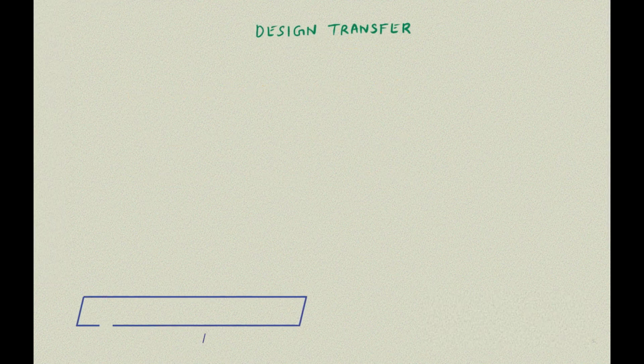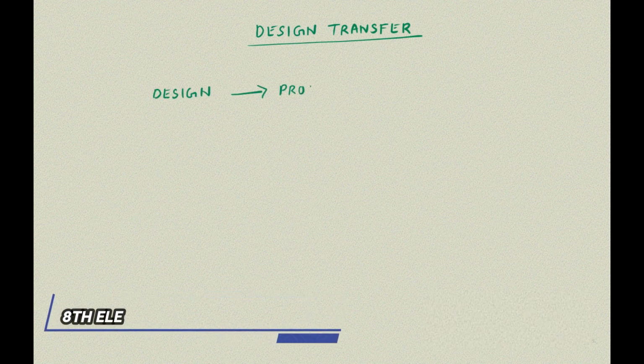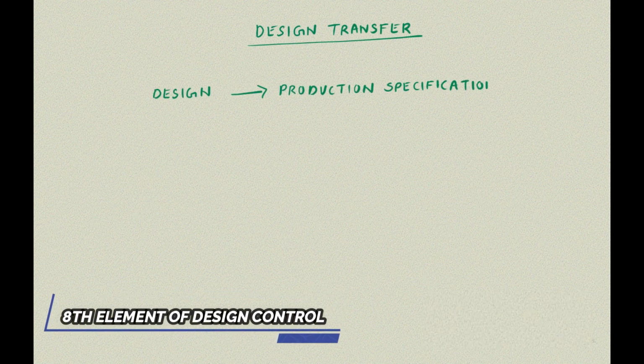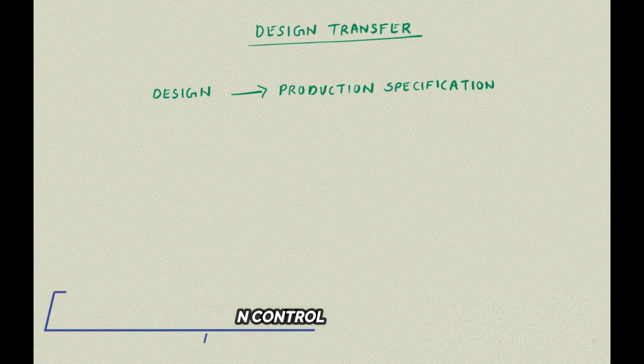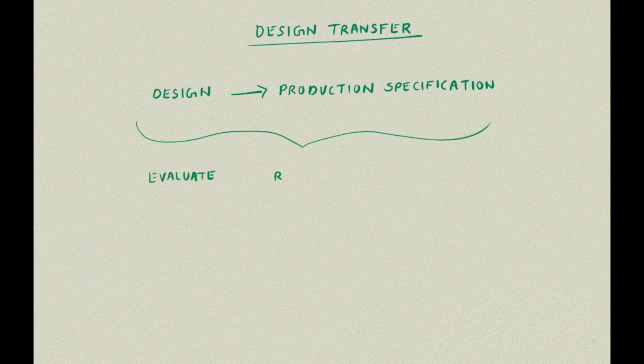Next is design transfer. The company should establish and maintain a procedure to ensure correct design transfer to the production specifications. Basically, we ensure that the design of the medical device is correctly translated to the production specification at this stage. So at this stage the device is advancing successfully from product development to manufacturing.